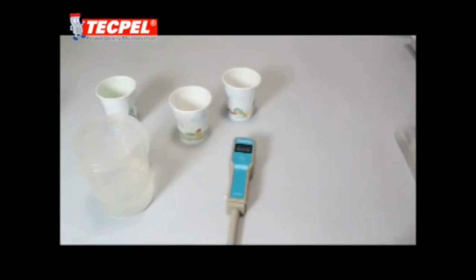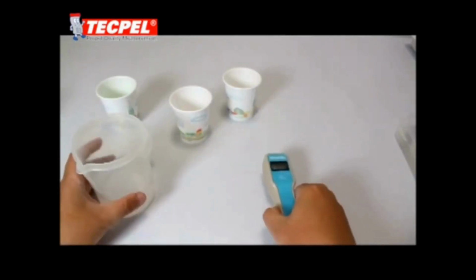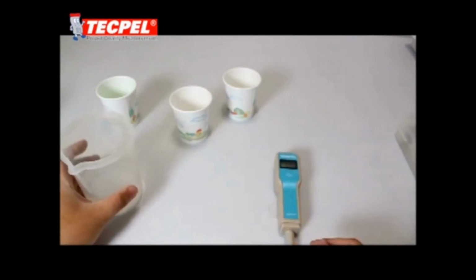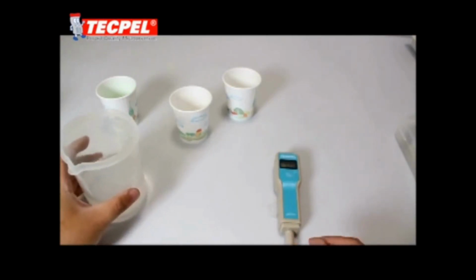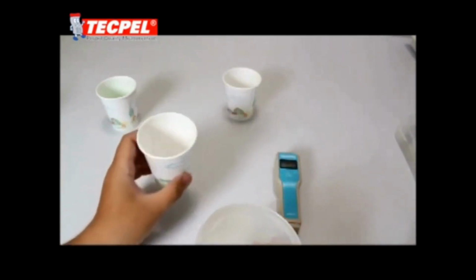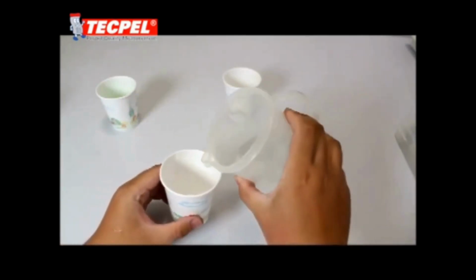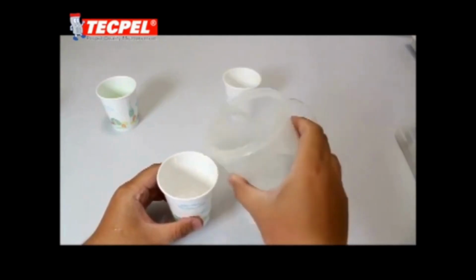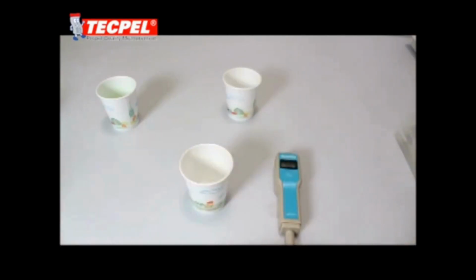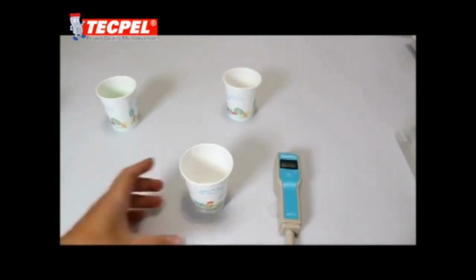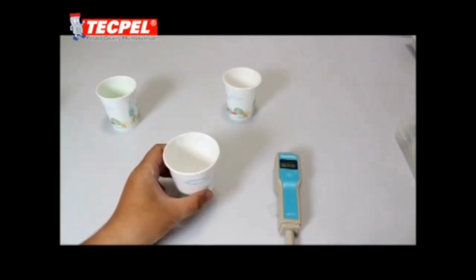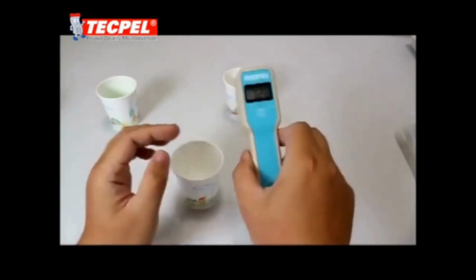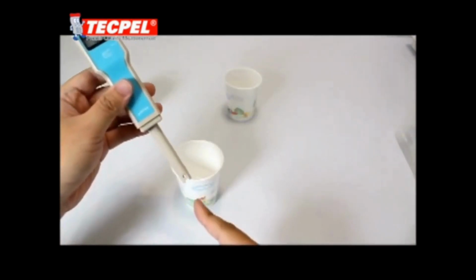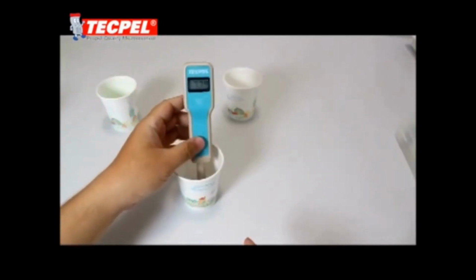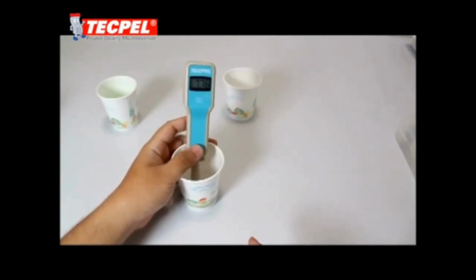Let's start with a simple and common example, measuring tap water. Tap water in most households typically falls around pH 7 and is slightly alkaline. Pour about 1/3 of a clean cup of water. You don't need a large amount, just enough to immerse the sensor. Before measuring any sample, always rinse the sensor to ensure accuracy. Then place the sensor into the tap water. After a few moments, the reading will stabilize. You may see a value between pH 7.5 and 7.6, which is considered normal for household tap water. Once the reading stops fluctuating, you can record the value.